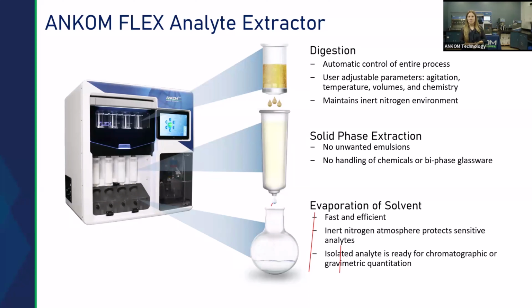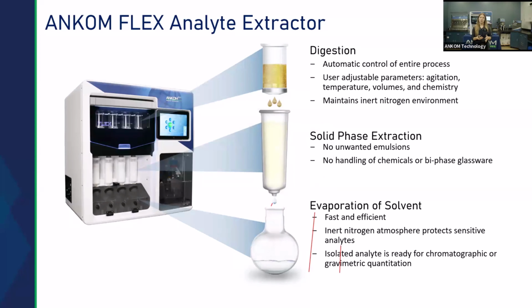In some experiments, we want to use the extracted oil to conduct additional tests. Is that possible for the XT15? So that's a great question. It is not possible with the XT15 because it is an indirect method, so we do it gravimetrically by weight loss. However, I am going to be sharing in this next section our Flex Analyte extractor, which is our newest piece of equipment. This piece of equipment runs total fat analysis and does capture that oil for you, so I'll elaborate on that in these next few slides.